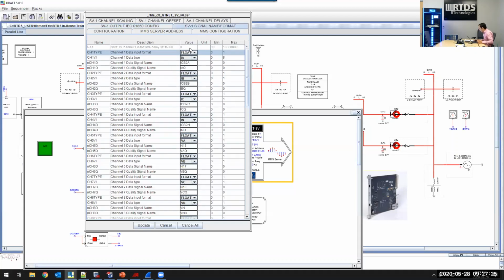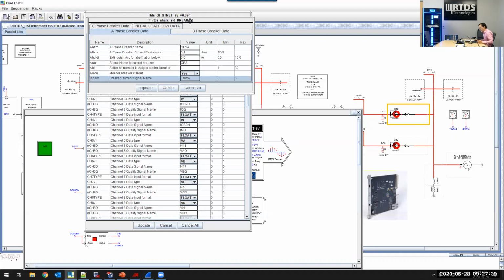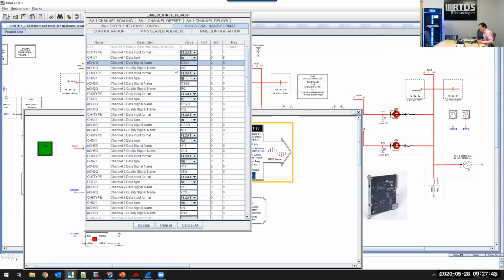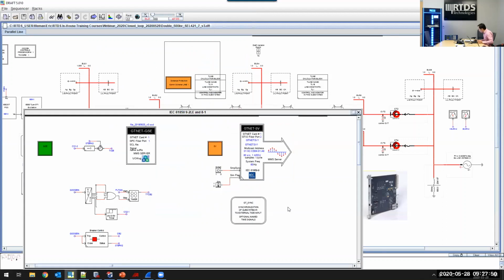The variables representing the voltages and currents at breaker 2 are entered in this name and format menu tab here. As you can see, for example, the channel 1 current is from the breaker 2 A phase current here. Similarly down for the other phases, and the voltages are from this bus here. Now let's have a look at this GTSync component here. Most of the time for sample value related applications, the publisher and the subscriber need to be time synchronized. In RTDS, we have a hardware called GTSync, developed for use in situations where synchronization between the simulator and external devices is required.